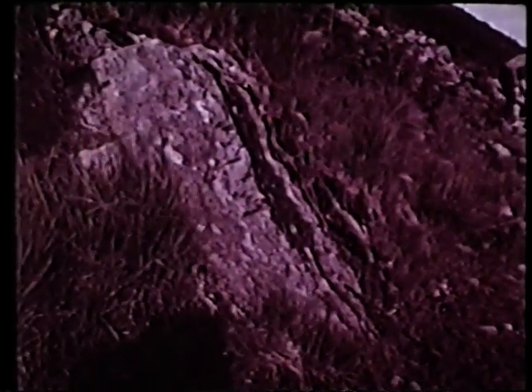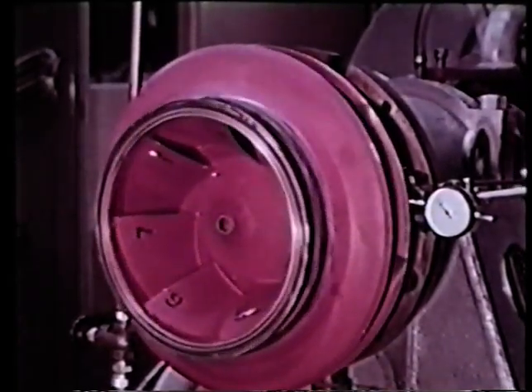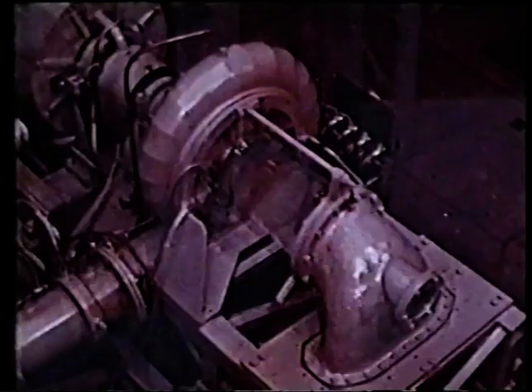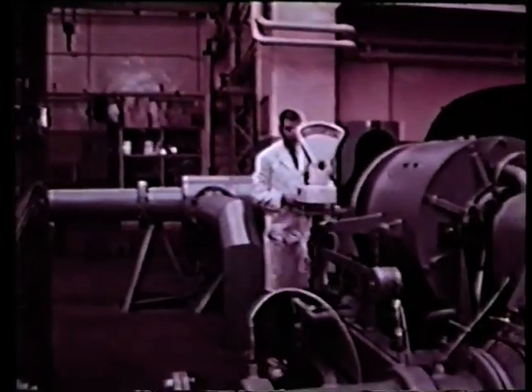And while civil engineers planned for work above and below ground, mechanical and electrical engineers were studying problems of design. Runner tests on homologous models would show if the same hydraulic machines could be used as pump and turbine, so cutting the cost of plant, at the very high head which Cruachan made it possible to use. The single reversible runner would have to be capable of lifting 6,000 gallons of water per second through 1,200 feet in one stage, much higher than had previously been attempted. Efficiency tests on model after model resulted in hydraulic profiles so well suited to both modes that the product efficiency equaled that of some alternatives using separate pumps and turbines.